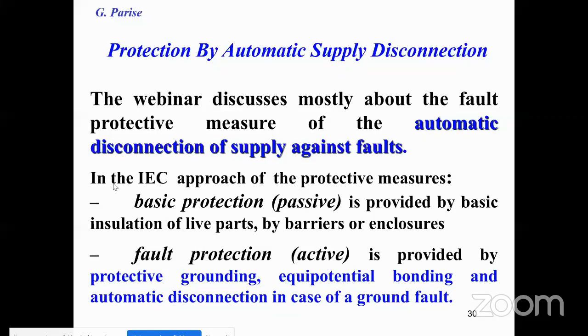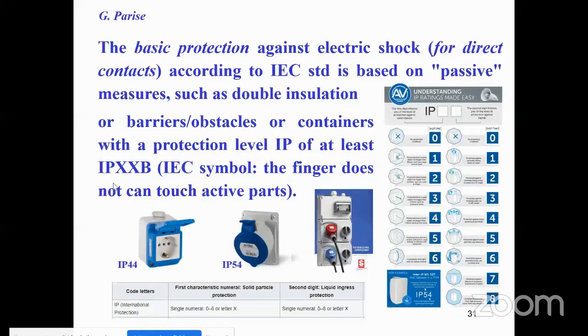That is, if we have equipment, and this equipment is class 1, it has to be connected to ground, to earth. It is important to organize the grounding connection and to adopt an automatic protective device that has to be organized to trip correctly if there is a fault. And so basic protection against electric shock for direct contact, according to IEC, is based on passive measures, such as double insulation, barriers, obstacles, or containers with a protection level IP of at least IPXXB.